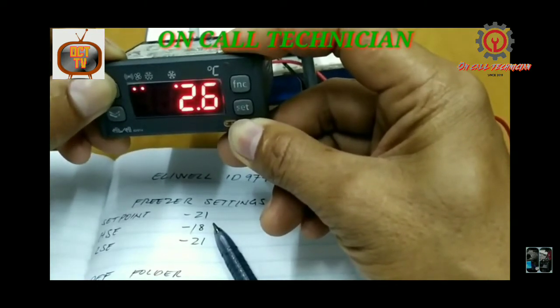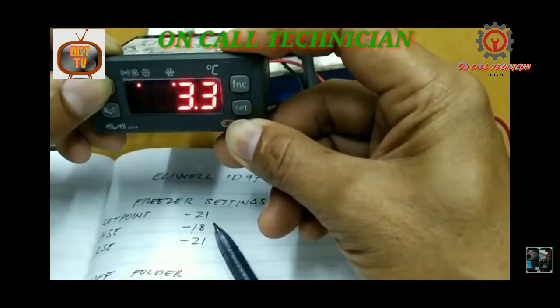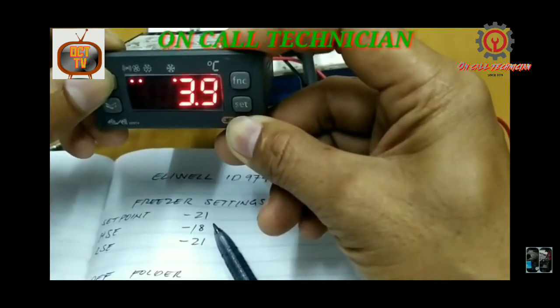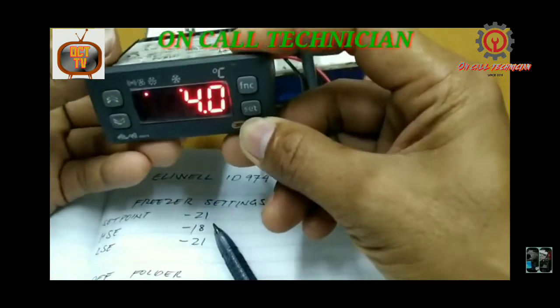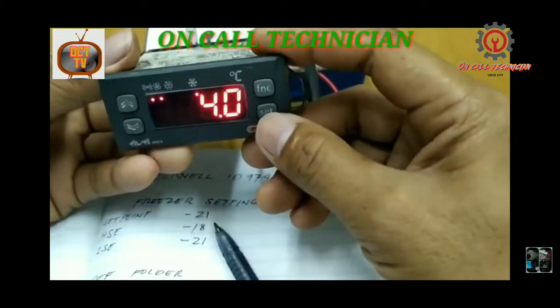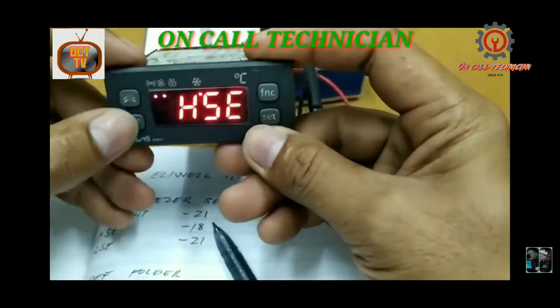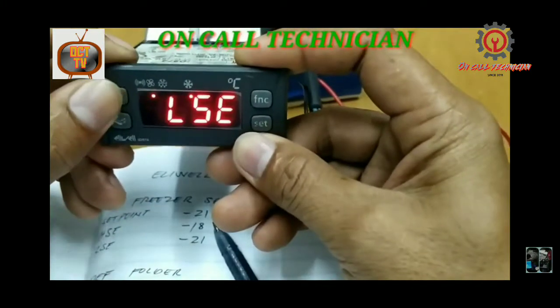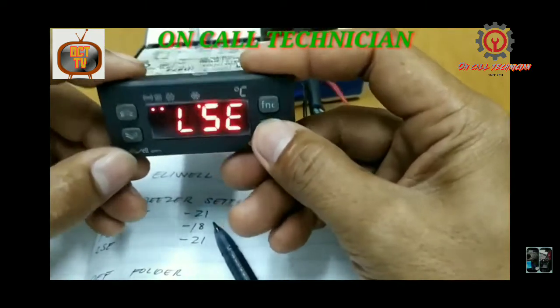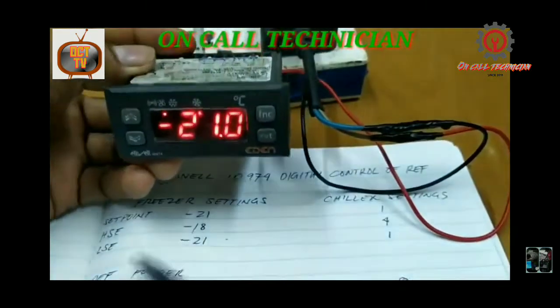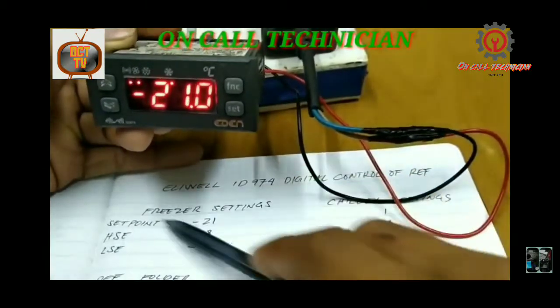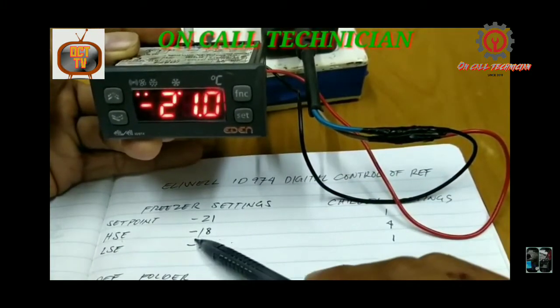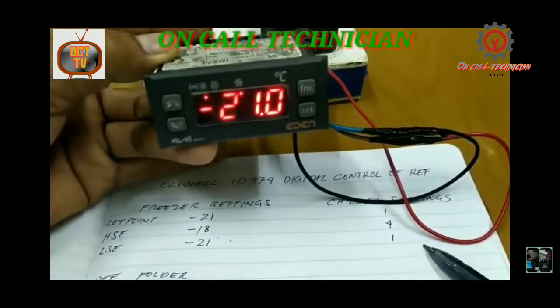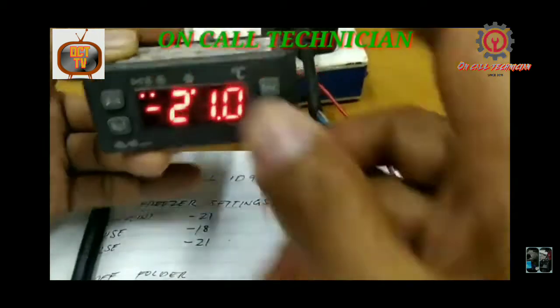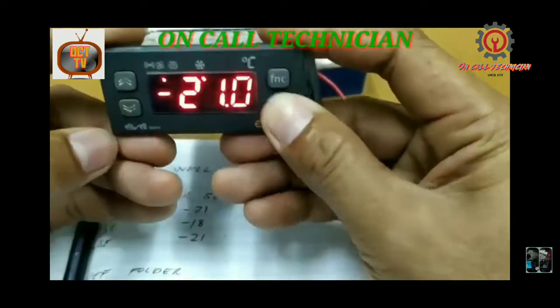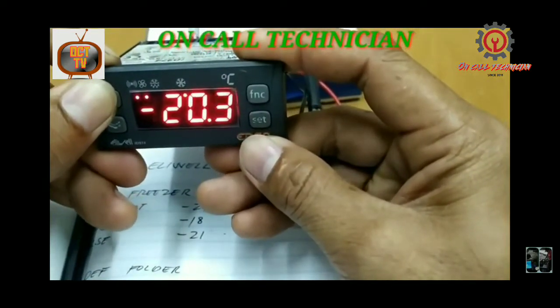Going up to 2.6, 2.9, 3, 3.3, 3.5, going to +4. So this is our HSE, which is the highest temperature, and let's locate the LSE. The LSE is the minimum set point. In Dixell this is LS, and in Eliwell this is LSE. It's set to -21. Again, let's press and change it.